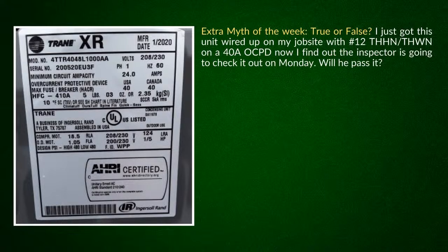That's why the National Electrical Code gives you permission to go directly off the 75 degrees C column. So you go over to the 75 degrees C column, number 12 is good for 25 amps. You go over there, maximum overcurrent device, 40, boom. There you got number 12 on a 40 amp breaker, good to go. There is a little snafu on this that I talked to James about before and went over with some of the other code teachers. There are certain times where a 40 amp overcurrent device won't accept a number 12 conductor, but that would be the only way that would make this a code violation.